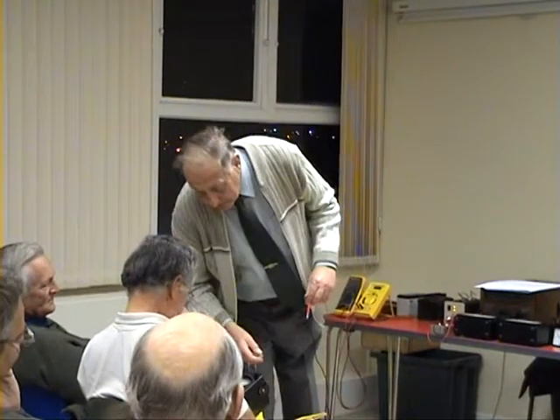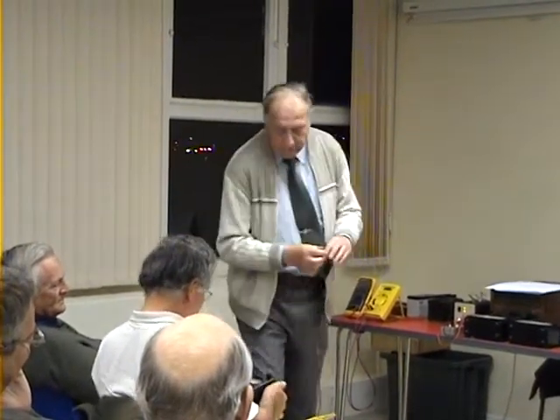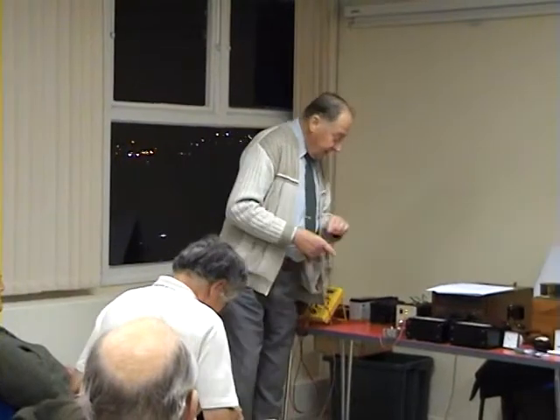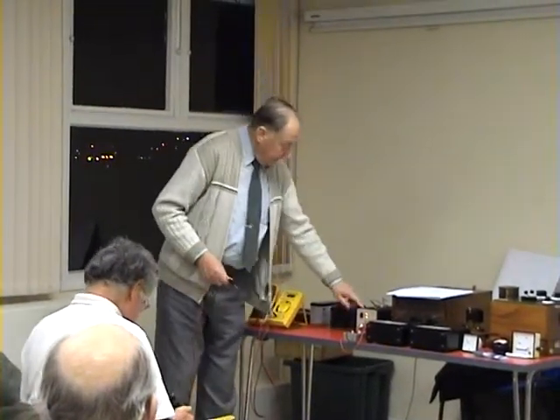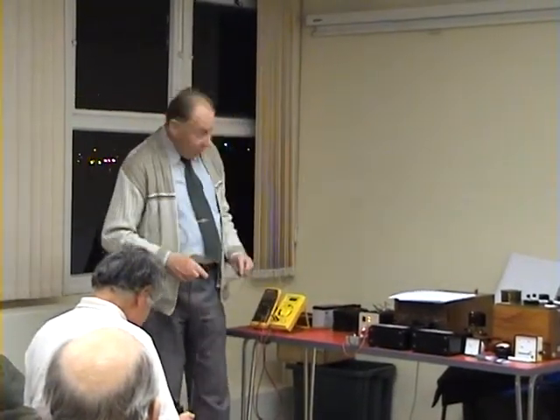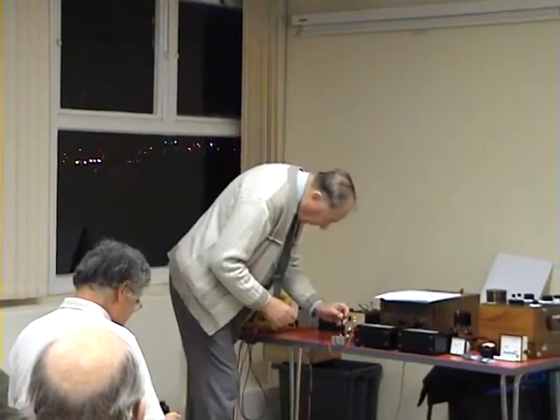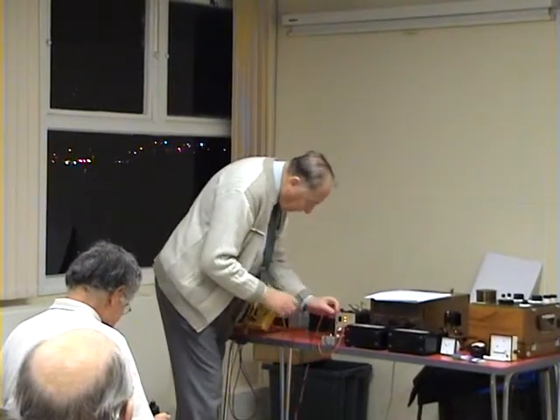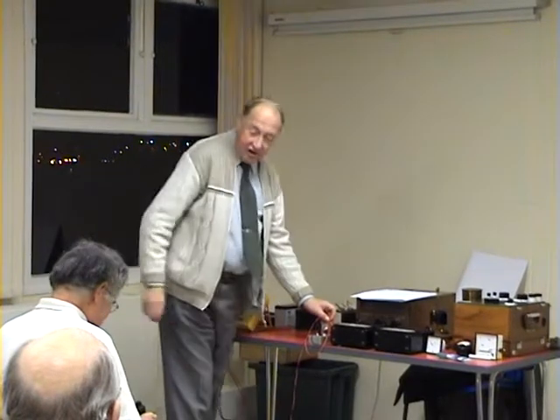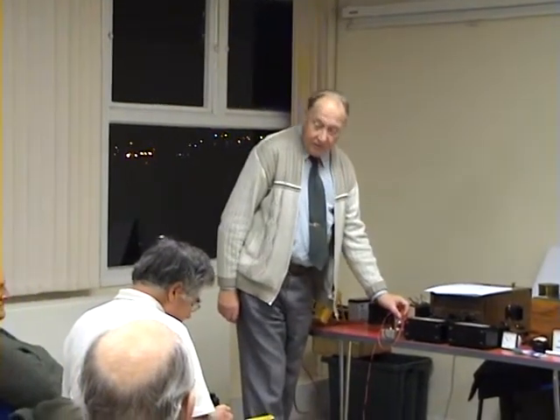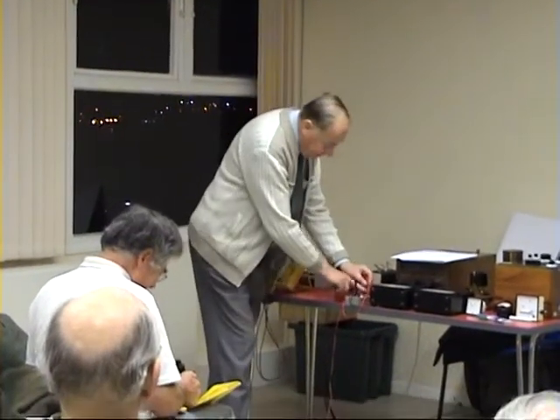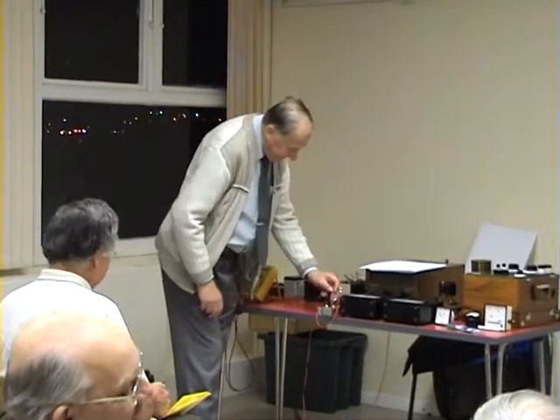Right, okay, it's switched to the 10 volt range. We're on there already, yeah that's it. You're reading off the 10 volt now, DC 10 volts, that's it. Horizontal, right, there we go. This is a voltage standard, this is. So I'm going to plug that in there, and that into there, and it says - oh golly gosh - 9.5, yeah, 9.8, near enough. Can we have that 10 volts? Yes.